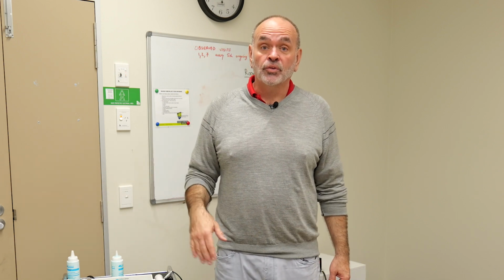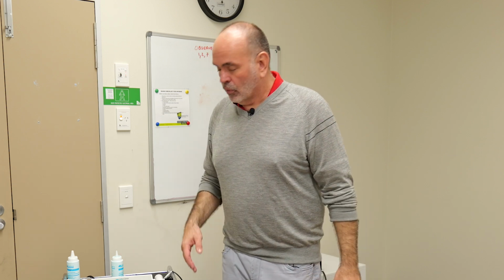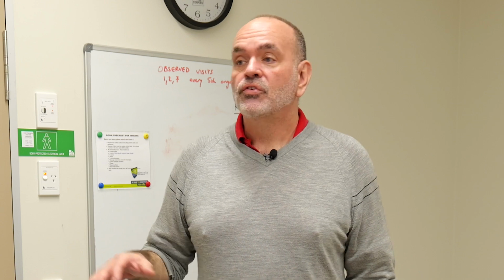We can also adjust the machine to deliver pulsed ultrasound, right? So we can change what's called the duty cycle. So we can use 100% duty cycle where that transducer is making sound the entire time, delivering energy the entire time, and that's going to create the most heat. Or we can use a pulse setting where we can have the machine on 50% of the time and off 50% of the time, which allows the tissues to dissipate some of the heat, so the circulatory system to dissipate some of the heat and control temperature that way.